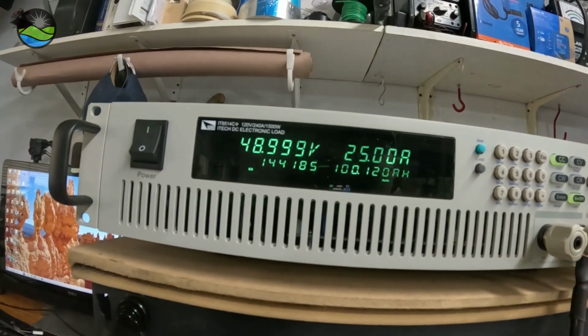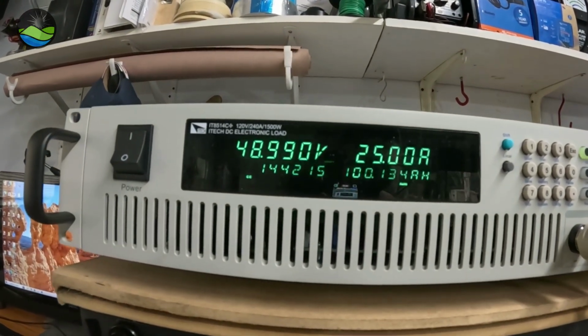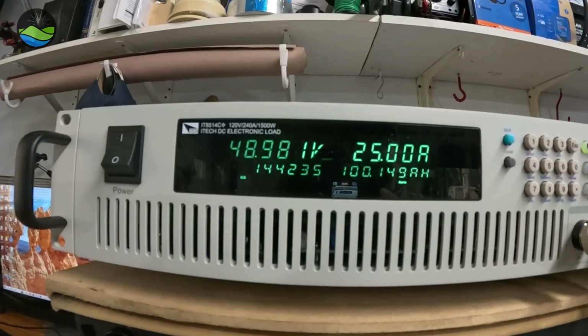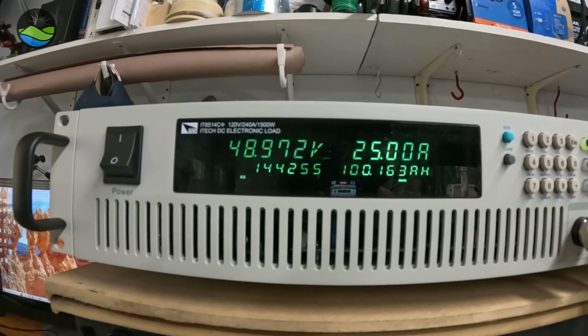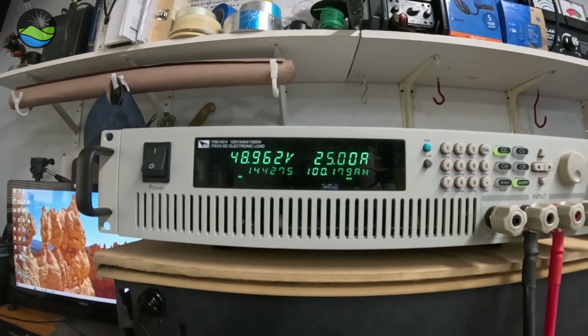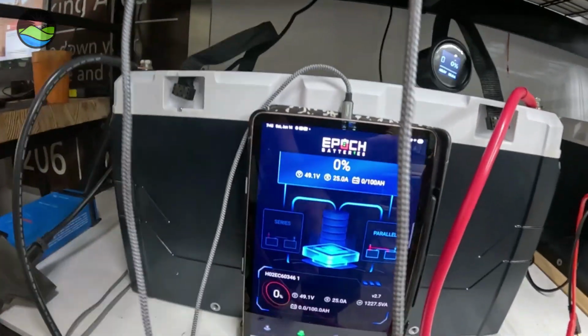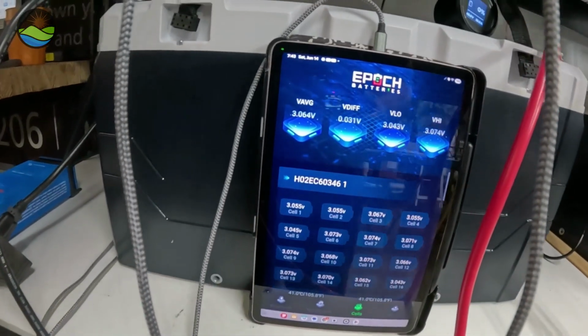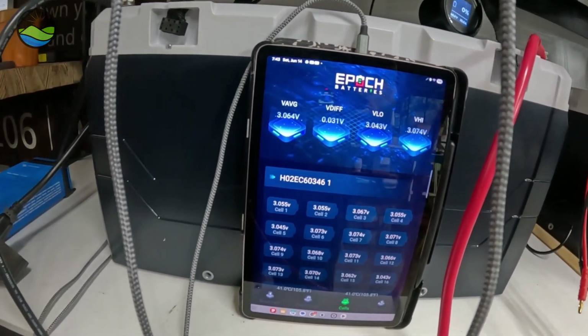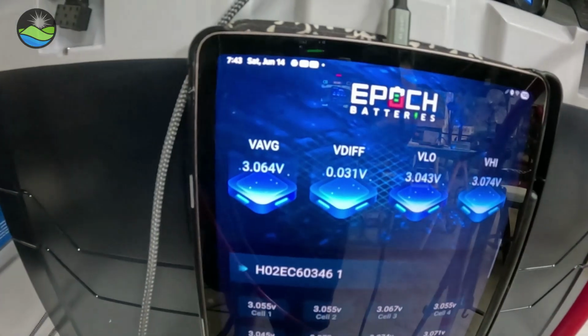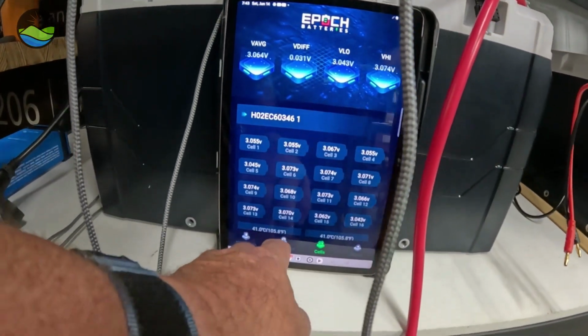So our voltage is starting to nosedive now. You can see at 48.9, and you can see it really start to nosedive. That tells me we're in the lower knee, and we're starting to really fall. So we're over 100 amp hours, that's good. Still above 3 volts though per cell. The VDIF is growing slightly.